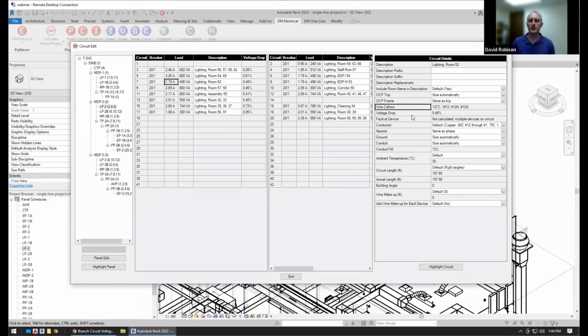Next, we display the wire size. So we give you the wire callout. Then we give you the voltage drop on the branch circuit and the fault calculated at the device. The fault really only makes sense when you're talking about a specific device, so a single piece of equipment. So if you have more than three pieces of equipment on the circuit, we're not going to calculate a fault. We're just going to say it's not calculated. If it's one, two, or three, we actually do calculate a fault.